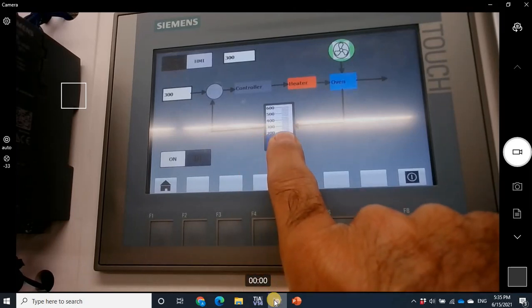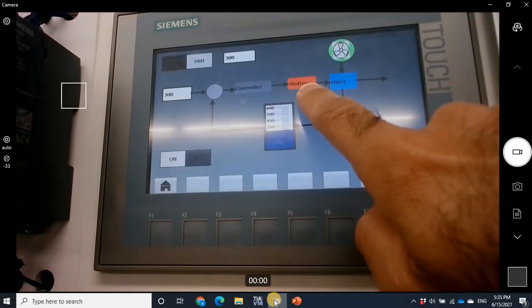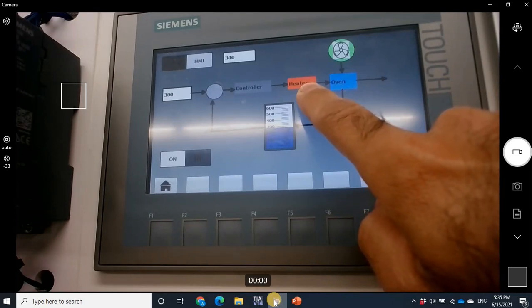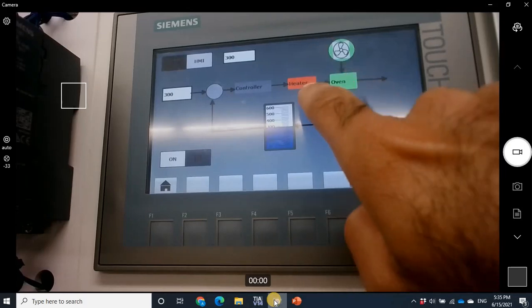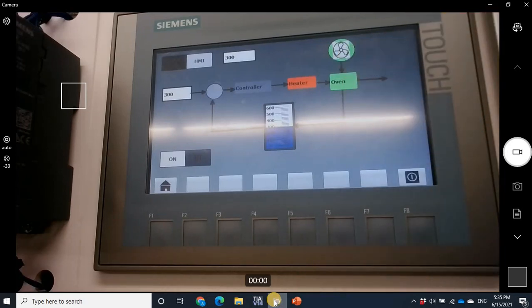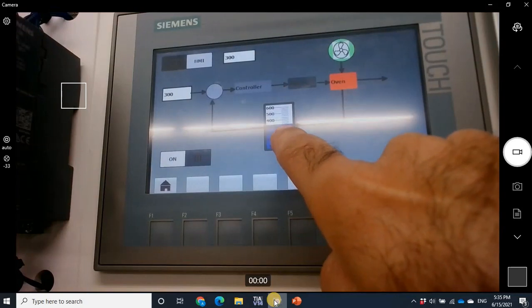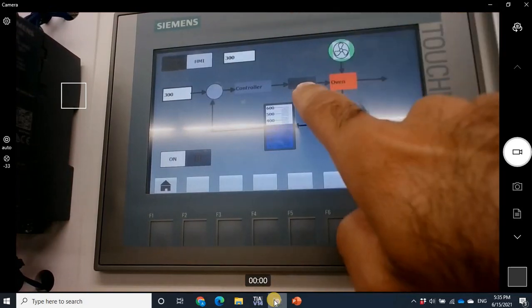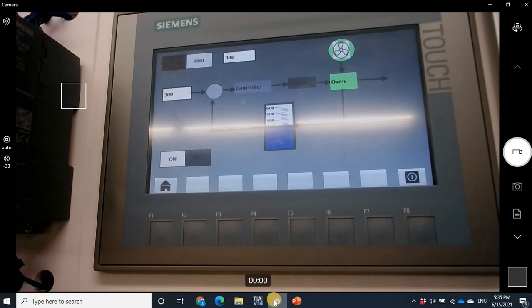When the temperature is low the oven is blue (cold) and the heater turns on, so the temperature increases. Somewhere in this range the heater is still on but the temperature is within the acceptable band — within five percent of the set point. Since the heater remains on, the temperature continues rising until it is 15 percent above the set point, at which point the heater turns off. The control system then works to keep the temperature approximately within this range.